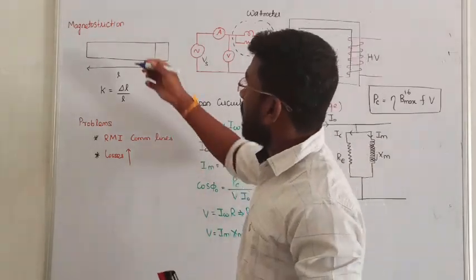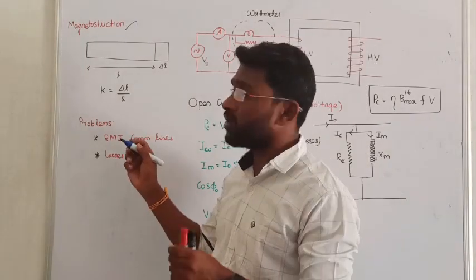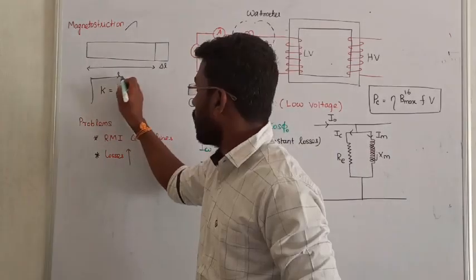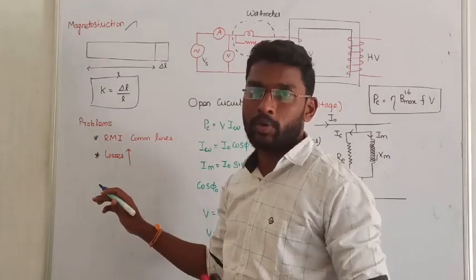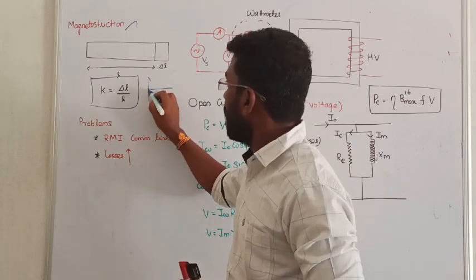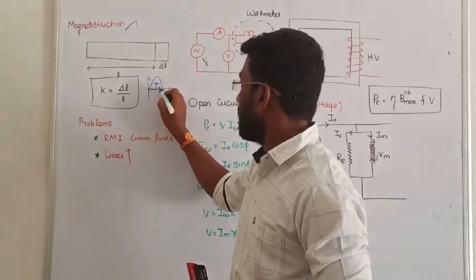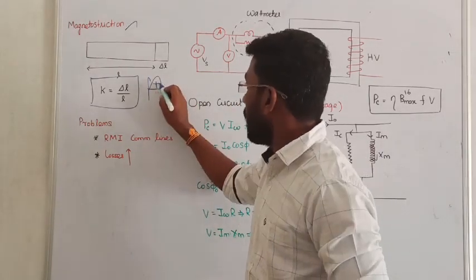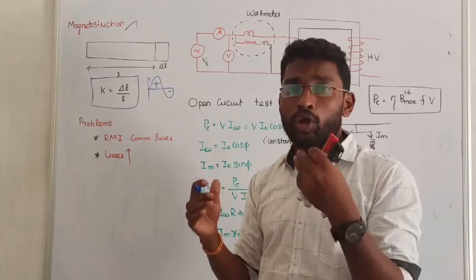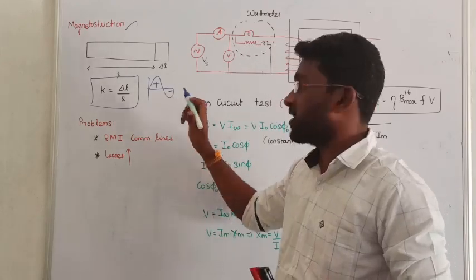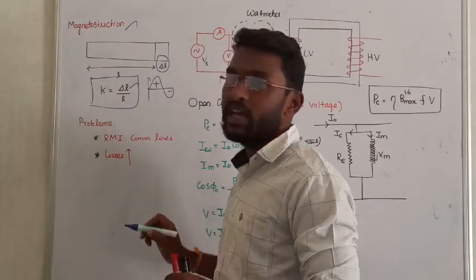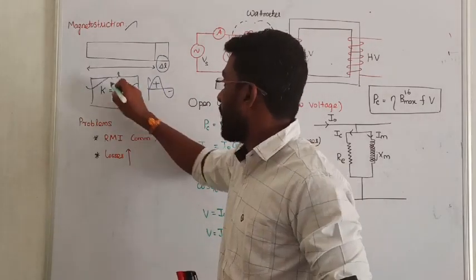That is called magnetostriction. In the transformer, magnetostriction causes a humming sound. We can define K as the magnetostriction coefficient. When we apply an alternating AC signal — positive and negative — for the positive cycle the core will be magnetized, and for the negative cycle the core will be demagnetized. During this process the core will vibrate, producing a humming sound. The actual core dimension will change due to magnetization and demagnetization; the core will expand by dL due to the actual length of the core. That is called the magnetostriction coefficient.